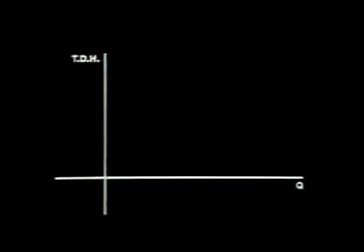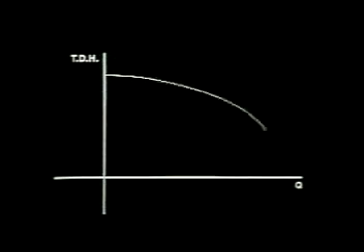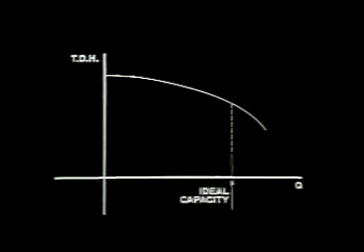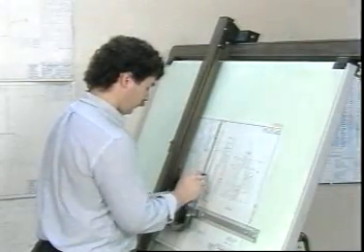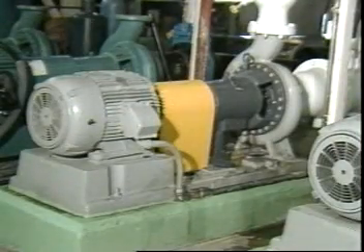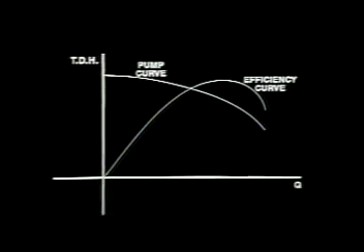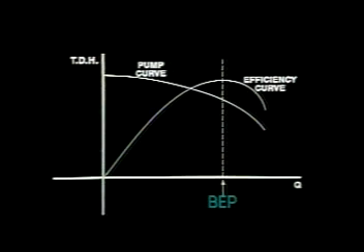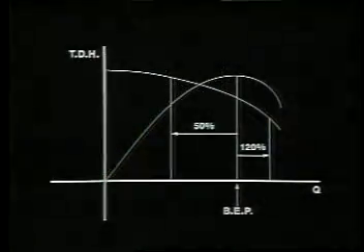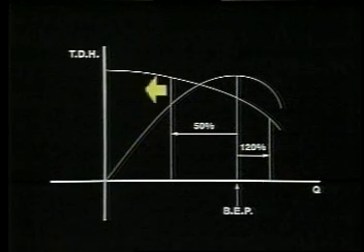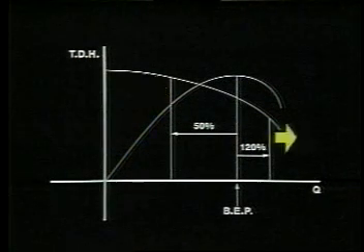This is why it is simpler to discuss the performance of a pump in terms of head rather than pressure, since head applies to every liquid regardless of density. Every centrifugal pump has a capacity at which it works best, sometimes called the ideal capacity of the pump — a direct result of the design criteria used. If the pump operates at other than ideal capacity, the hydraulic design is compromised in a number of ways. The best known of these is efficiency, which steadily drops as the pump is operated away from its ideal capacity. Because of this, the ideal capacity is usually referred to as the best efficiency point, or BEP. Other compromises affect the stability of pump operation and are particularly detrimental at less than 50 percent of BEP or higher than 120 percent of BEP.